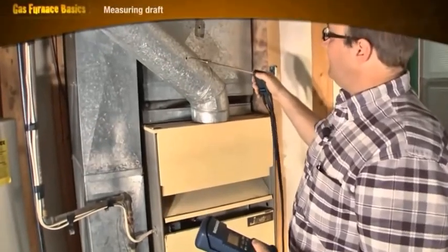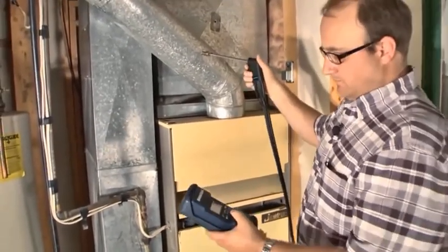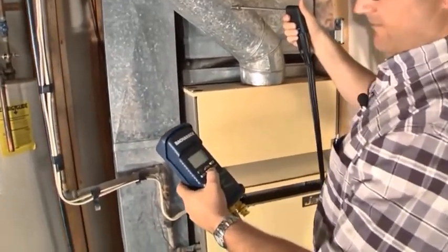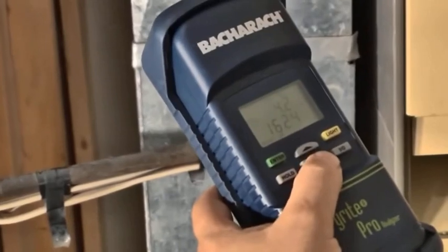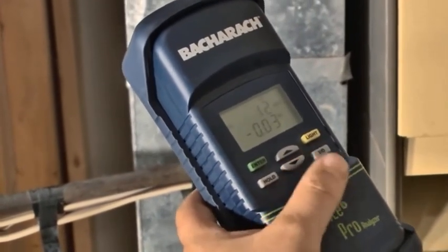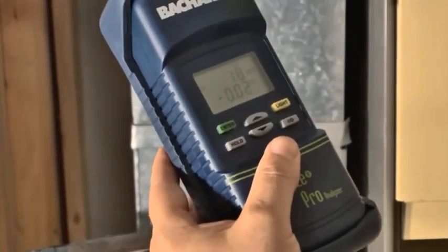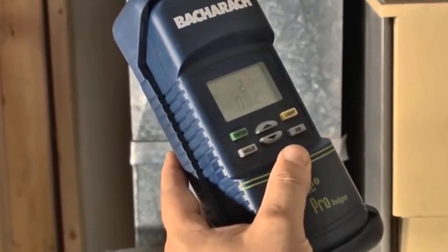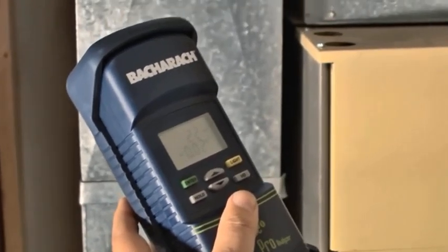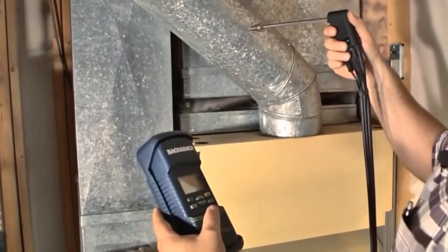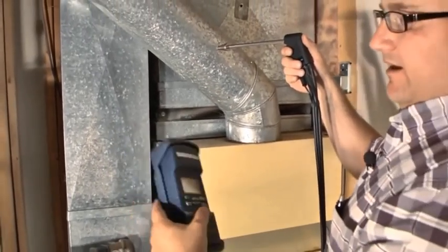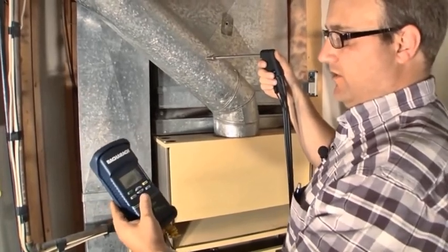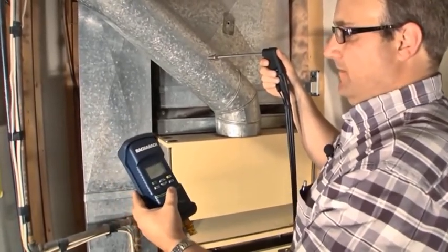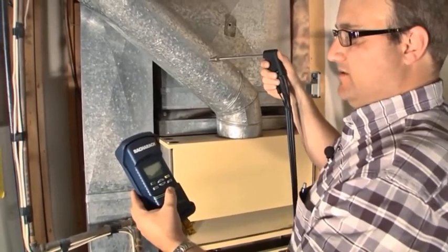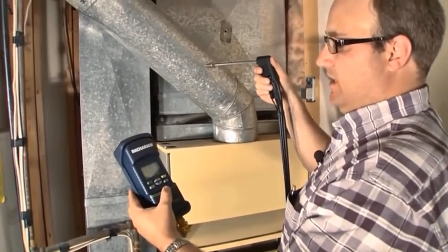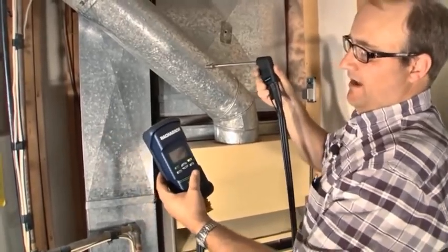Okay, we're going to use our combustion analyzer to get our draft reading and see how much draft we have. Okay, right now we're getting 0.03 inches, 0.02 inches of water column of draft. So we do have a negative draft. Right now we have all the doors that could be shut to this area that we're working in shut. We have all the fans running. We're creating the worst case CAZ, combustion appliance zone, with all the windows shut, the fans running, and we still have good draft.